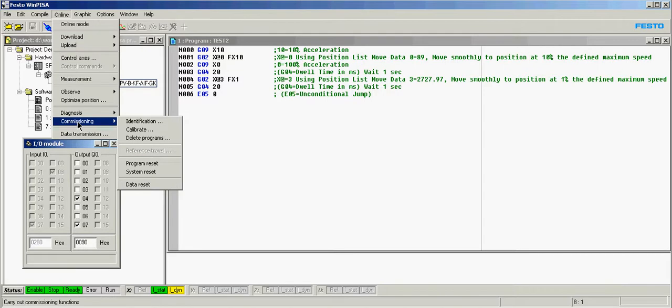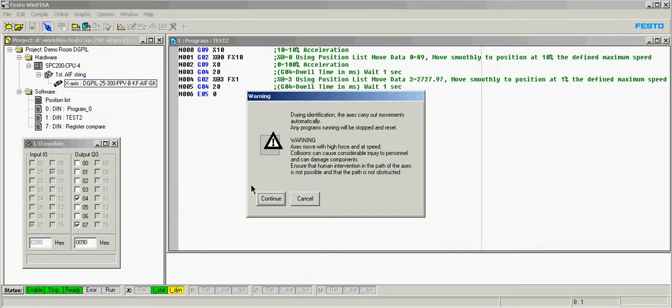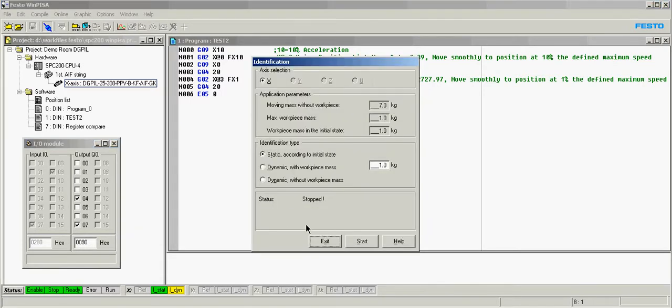The identification test is shown right here. Click identification, hit continue. You need to do, at minimum, a static and one dynamic, either with or without the workpiece mass. I'm going to do the static first.